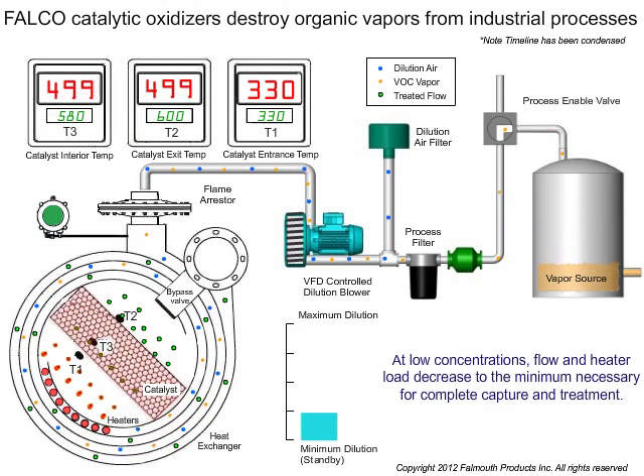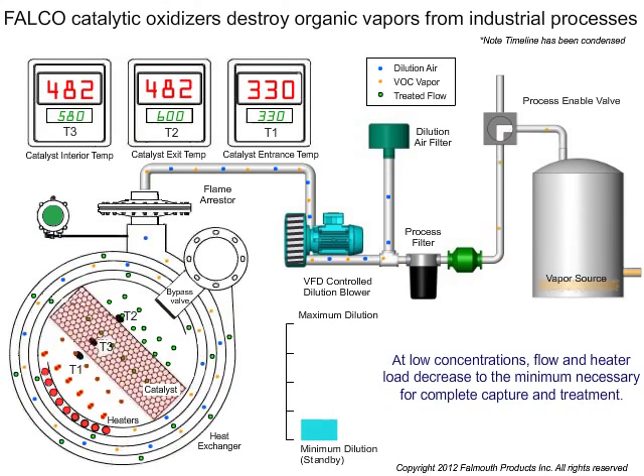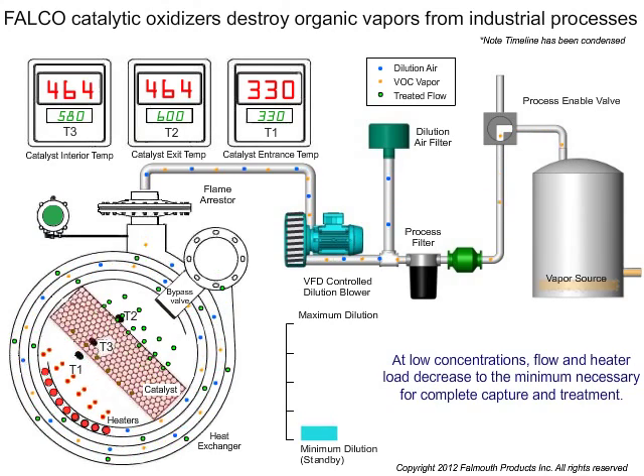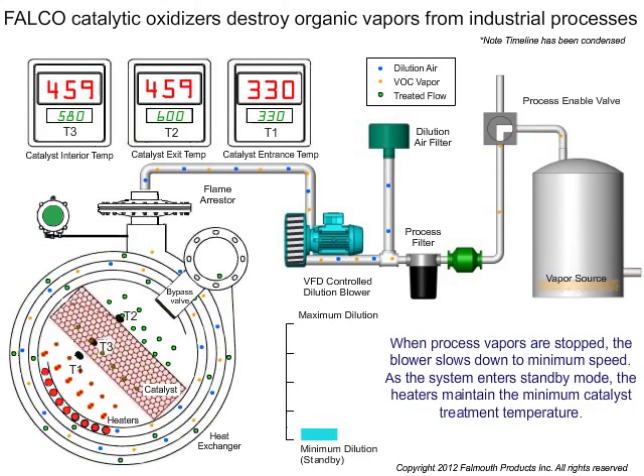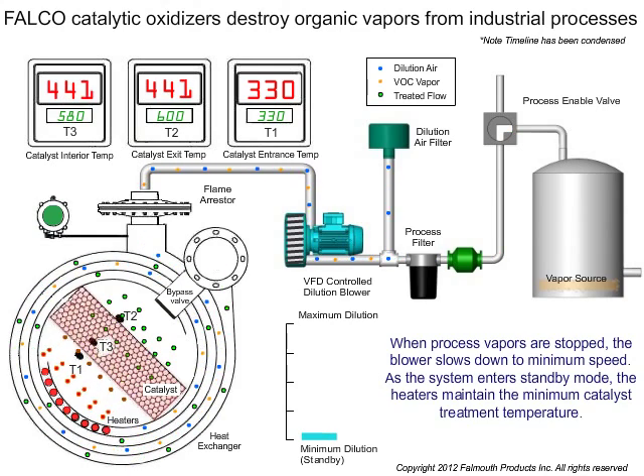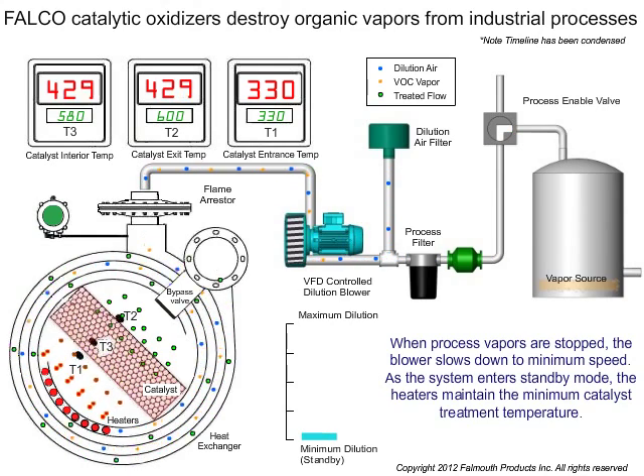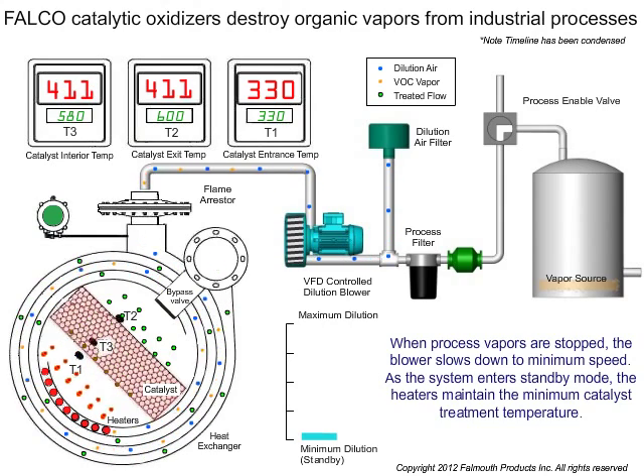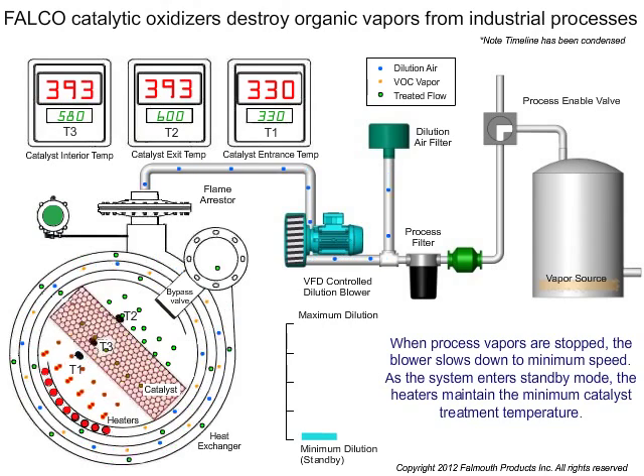At low concentrations, flow and heater load decrease to the minimum necessary for complete capture and treatment. When process vapors are stopped, the blower slows down to minimum speed. As the system enters standby mode, the heaters maintain the minimum catalyst treatment temperature.